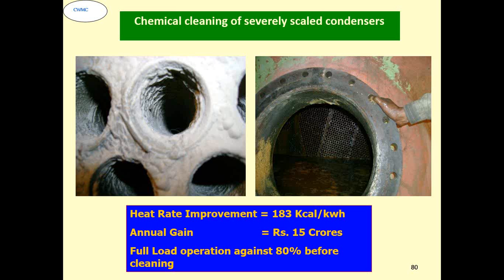Now this was a case of condenser scaling, calcium carbonate scale. The tubes had so much scale, the plant was losing heavily. They were not able to run the 210 megawatt unit to more than 150 megawatt, and their vacuum and everything was dropping. When we checked, we were not able to put our fingers inside the condenser tube, so much thick scale had taken place. So we chemically cleaned it, and what we gained out of that was almost 15 crore per annum. The plant gained, and they were able to operate the units at full load even during the peak summer.